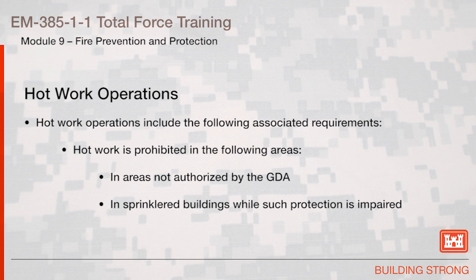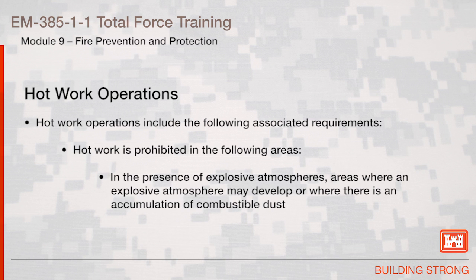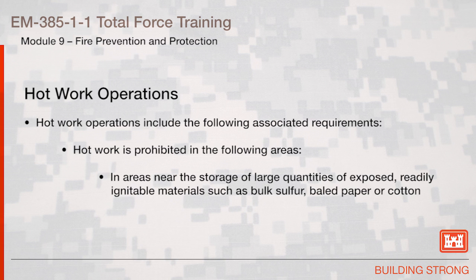Hot work is prohibited in the following areas: in areas not authorized by the GDA; in sprinklered buildings while such protection is impaired; in the presence of explosive atmospheres, areas where an explosive atmosphere may develop, or where there is an accumulation of combustible dust; and in areas near the storage of large quantities of exposed, readily ignitable materials such as bulk sulfur, baled paper, or cotton.